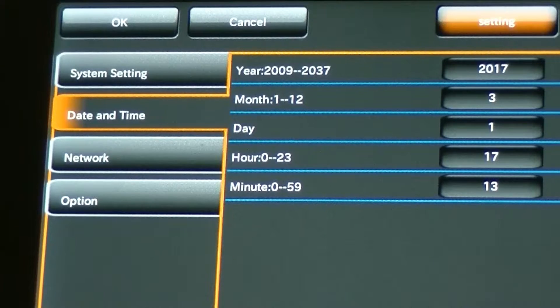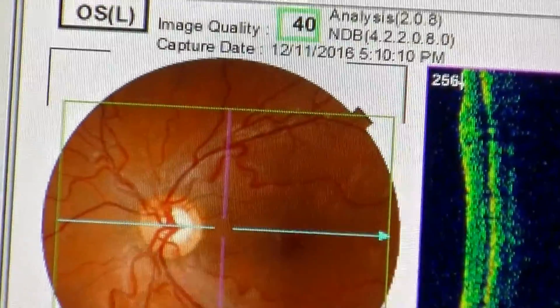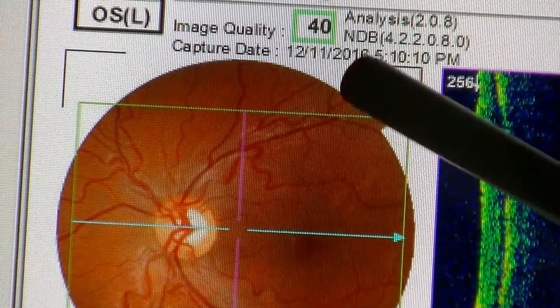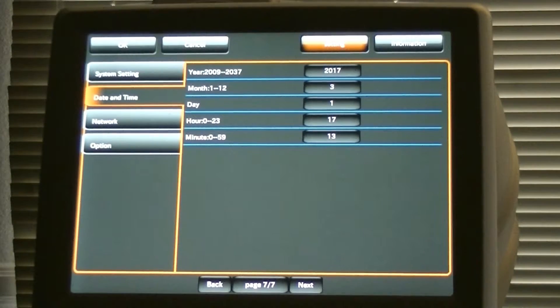Make sure it's correct. Then, once you do that, when you take the reading and look at the report, this date and time will match the time zone that you're in. Then it won't be off by two hours or three hours. And that is how you change the date and time on the 3D OCT Maestro. Thank you for watching, and I hope it was informative for you as it was for me. We'll see you next time.